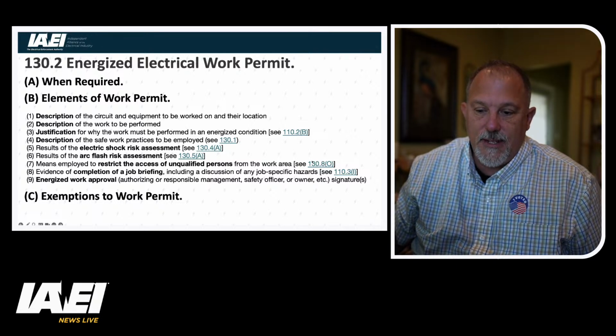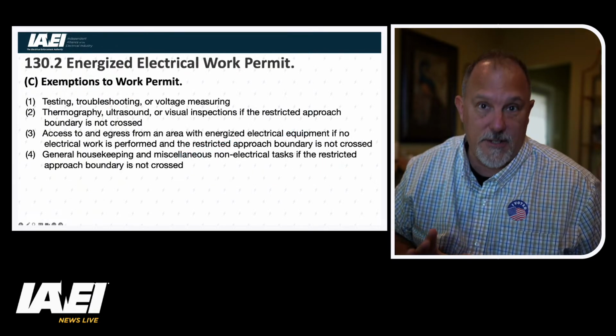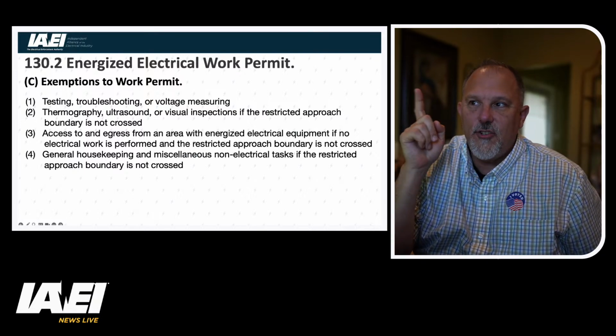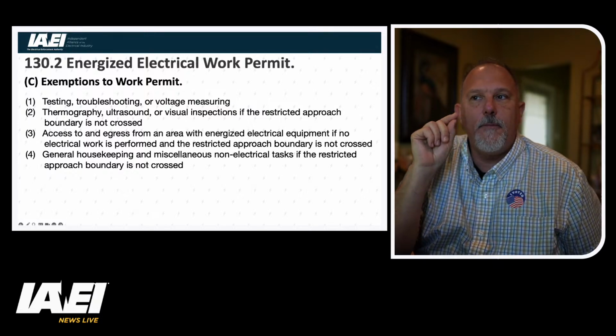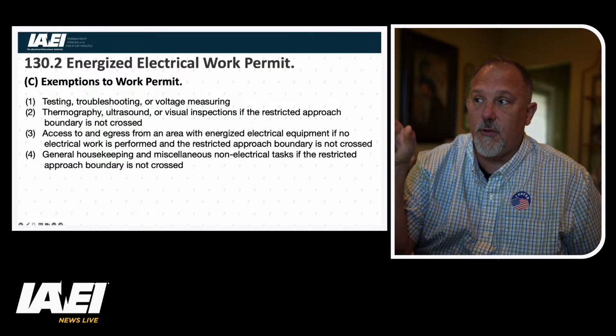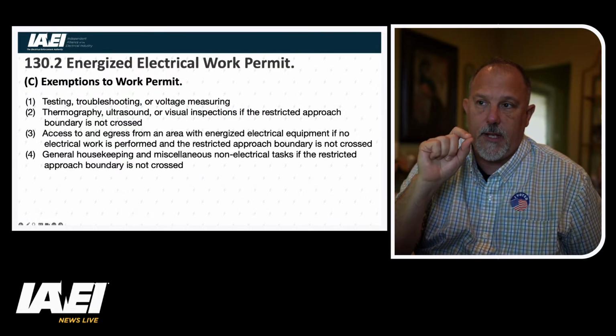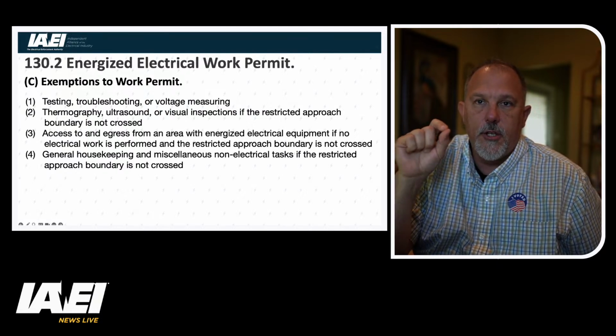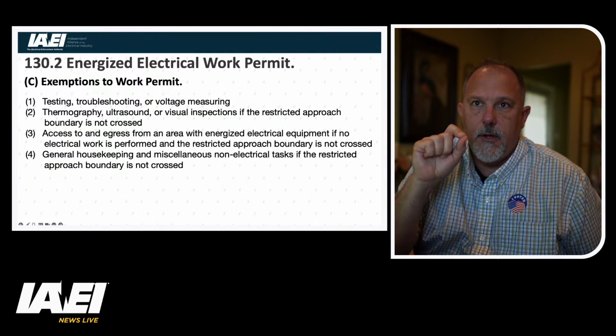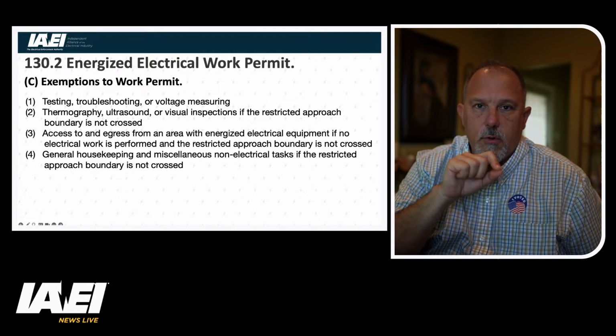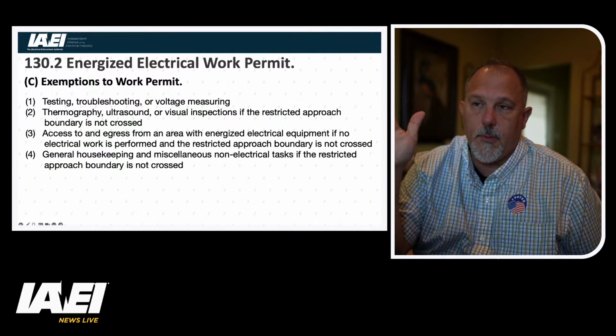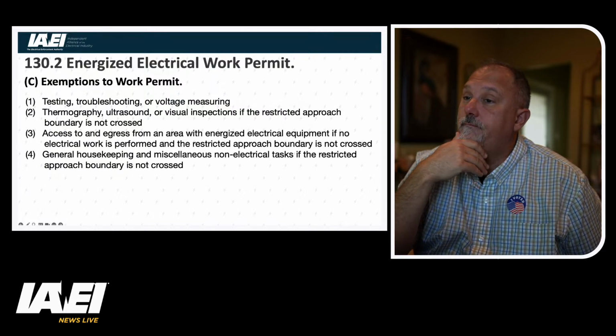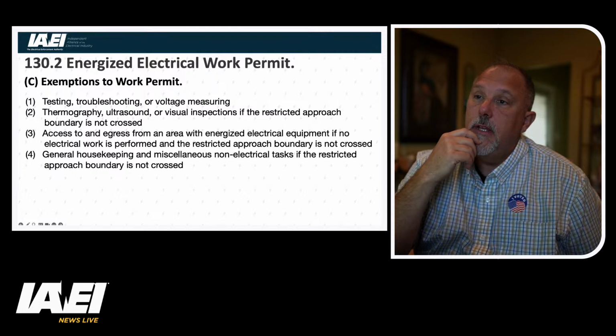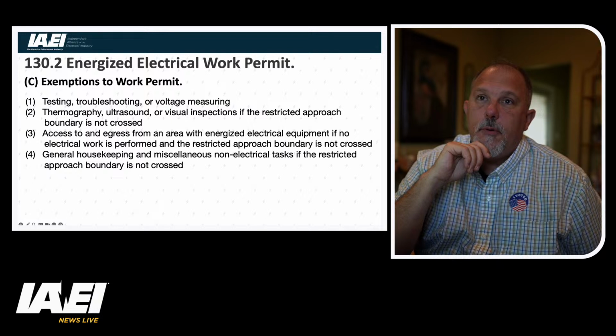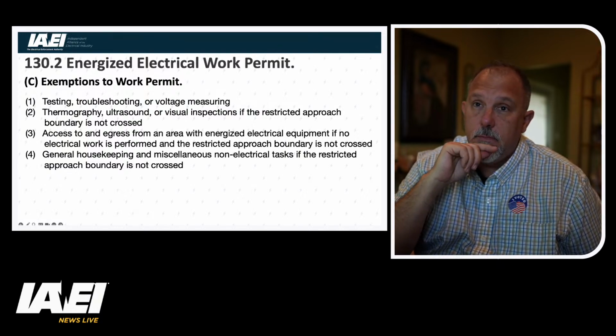Now there are exceptions. Let's take a look, because I thought the exceptions were exceptionally interesting. Testing, troubleshooting, or voltage measuring. Now, thermography is one of those. Ultrasound or visual inspections, if the restricted approach boundary is not crossed. So now I can conduct thermography with the doors open and say I don't need an energized electrical work permit if I am doing thermography. But what about the act of opening the door?